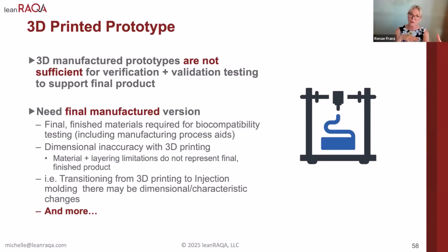One, if you're going from 3D printing to injection molding and your device requires biocompatibility testing, guess what? Those are two different materials and processes. And you're probably adding some coloring if you're going from 3D printing to your final device. That all has to go through biocompatibility testing. And if your device is sterile, you sterilize the device, then go through biocompatibility testing to see if it passes.